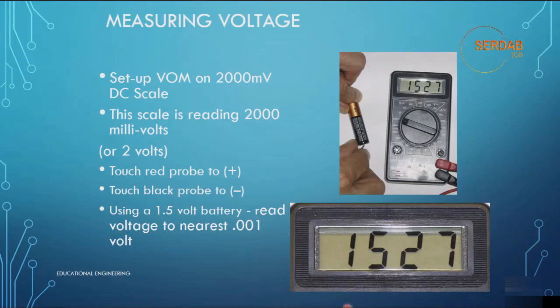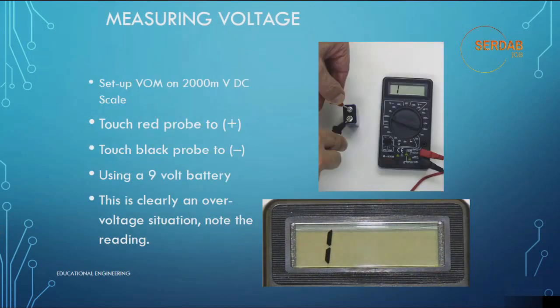Now let's look at another example. In this example, we are setting our voltmeter on the 2000 millivolt DC scale, and we are touching the red probe to the positive and the black probe to the negative side. We are using a 9 volt battery, and this is clearly an over voltage situation. Note the reading, it's 1. So you must know what happens if you use a scale that is too low for the voltage being measured.